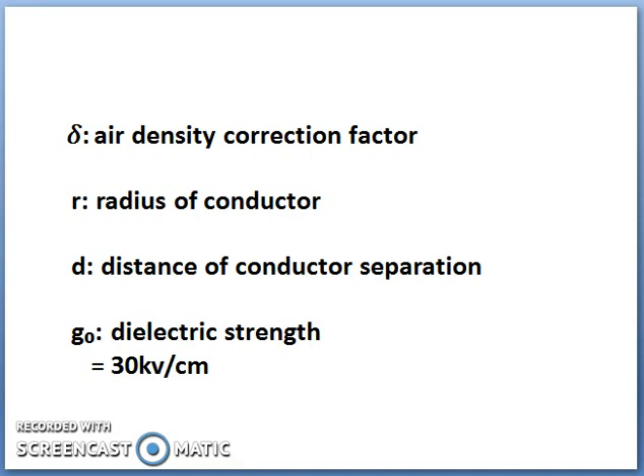Therefore, the final equation for critical disruptive voltage is: V = δ · M₀ · R · G₀ · ln(D/R), where G₀ is 30 kilovolts per centimetre, delta is 3.92B/(273 + T), M₀ is the irregularity factor, and ln(D/R) is the natural logarithm of the ratio of conductor spacing to conductor radius. This is the final equation for critical disruptive voltage.